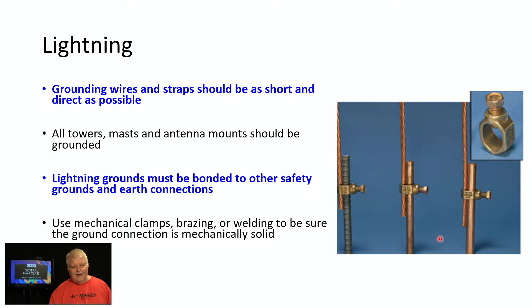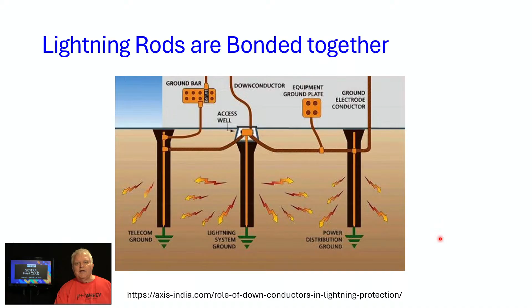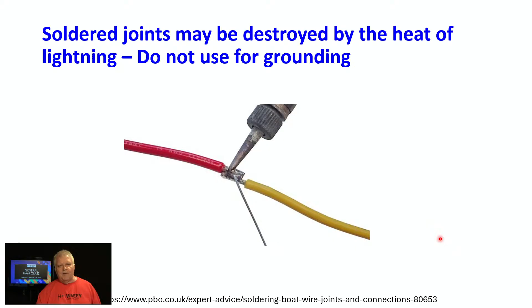should be bonded to other safety grounds and other earth connections using mechanical clamps or CAD welding, which is a high temperature welding process. Lightning rods bonded together keep the electrical potential all uniform throughout the system. You do not use solder to make these connections, because solder joints may be destroyed by the heat of lightning. So it's not appropriate in this case. But grounds are bonded together.